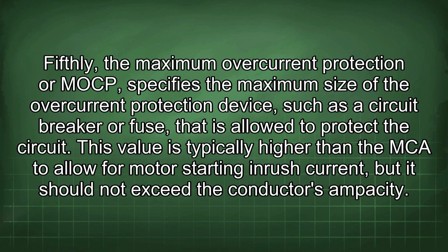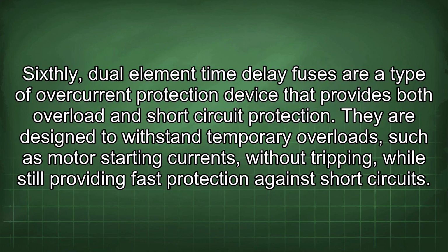the conductor's ampacity. Sixthly, dual element time delay fuses are a type of overcurrent protection device that provides both overload and short circuit protection. They are designed to withstand temporary overloads, such as motor starting currents, without tripping, while still providing fast protection against short circuits.